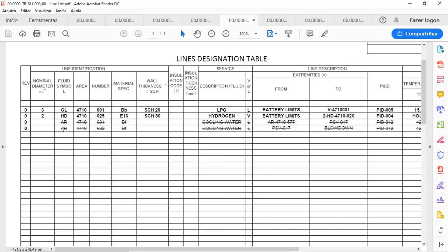I'll talk about the P&ID further, but the line list prevents the chemical process engineer from duplicating information for different things. For instance, I have a sheet B01 with line 001 and sheet F5 with the same line identification. So when you are developing your pipe instrumentation diagram, most often you do that using the line list side by side, and that will prevent you from duplicating information and making your job harder. There are intelligent P&ID softwares that do that automatically. But if you are in a small company, most often you will fill the line list manually.